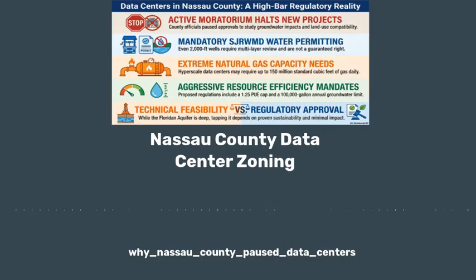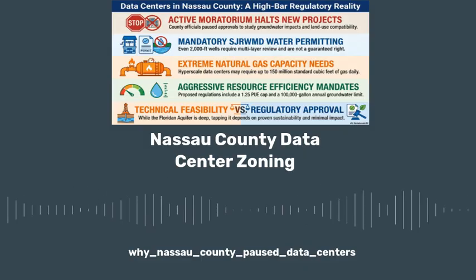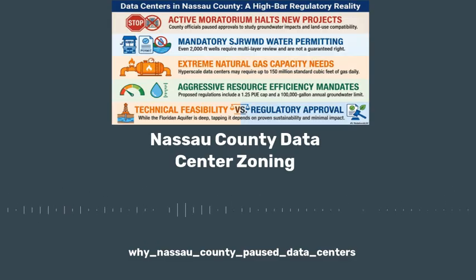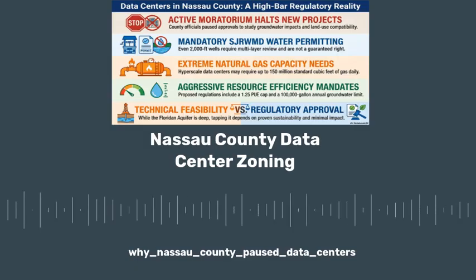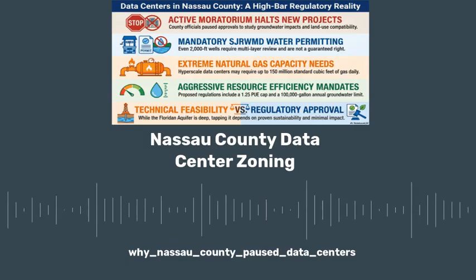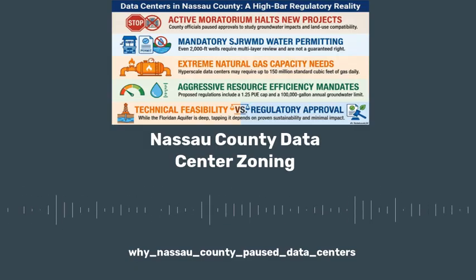And beyond the legal contracts, there's the raw physical engineering. Because if you tap a high-pressure line and start sucking out 750 blimps worth of gas a day, that has to violently alter the physics inside the pipe. Drastically. It is all about maintaining operating pressure. Natural gas doesn't just lazily float down the pipe. It is pushed by massive turbine-driven compressor stations spaced out along the route. If a gigawatt data center taps into the line and begins a massive draw, it creates a localized vacuum. The pressure in the main line plummets. And if the pressure plummets, the gas stops moving.